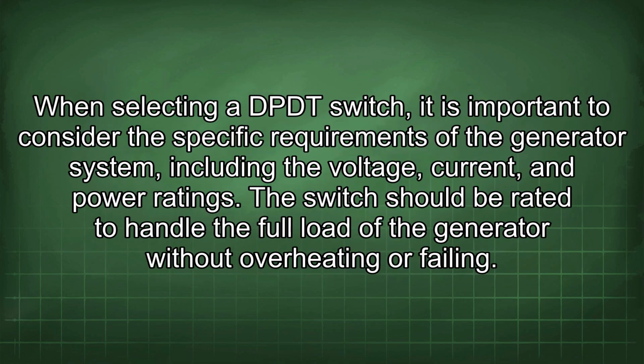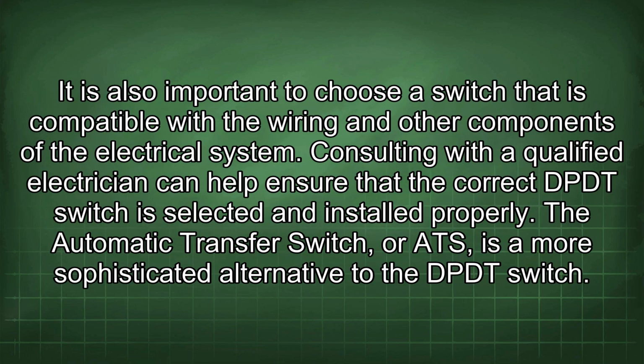When selecting a DP-DT switch, it is important to consider the specific requirements of the generator system, including the voltage, current, and power ratings. The switch should be rated to handle the full load of the generator without overheating or failing. It is also important to choose a switch that is compatible with the wiring and other components of the electrical system. Consulting with a qualified electrician can help ensure that the correct DP-DT switch is selected and installed properly.